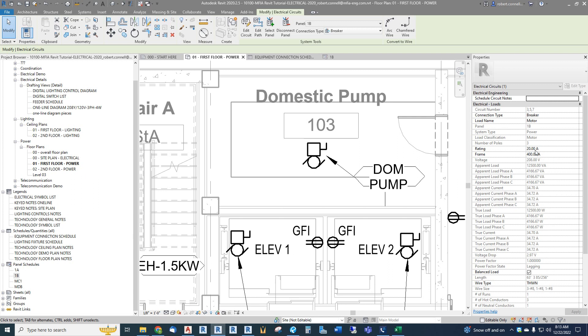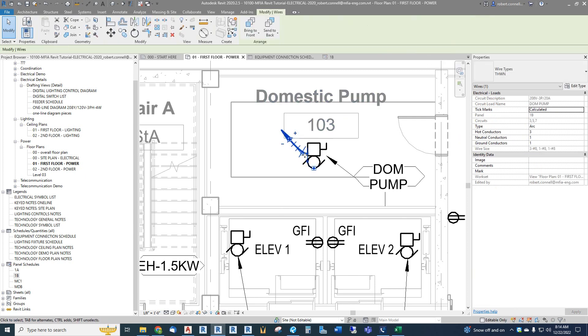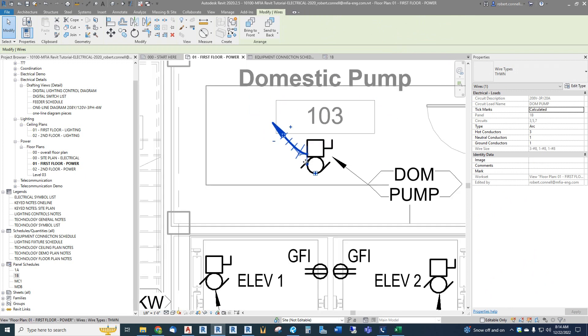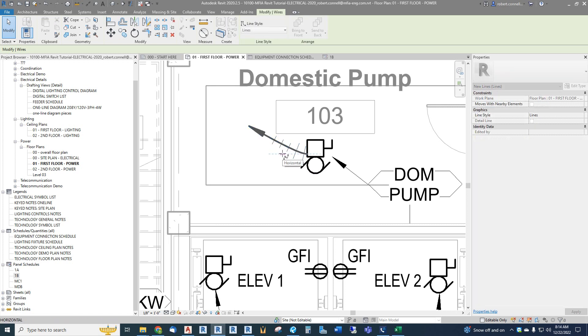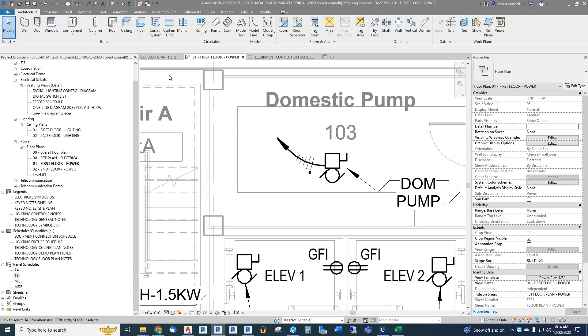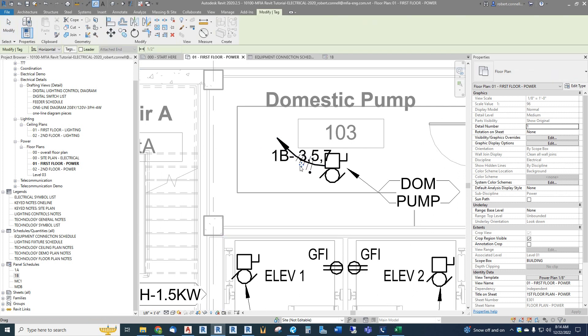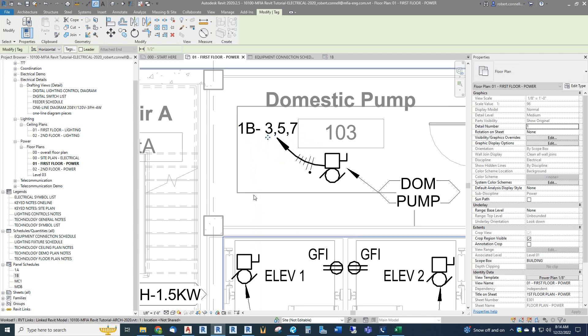In this case let's hook it up to branch panel 1B. We'll need to look at the breaker rating using charts and tables — that's a design decision. So we can fix the rating here. We want to label this as 'domestic pump' — we don't need to repeat the room since it's obviously in the pump room. From here I can draw an arc and see it attaches to the disconnect automatically this time. Let's center the wires so they display correctly, then tag it. It's a longer tag because it's three-phase.